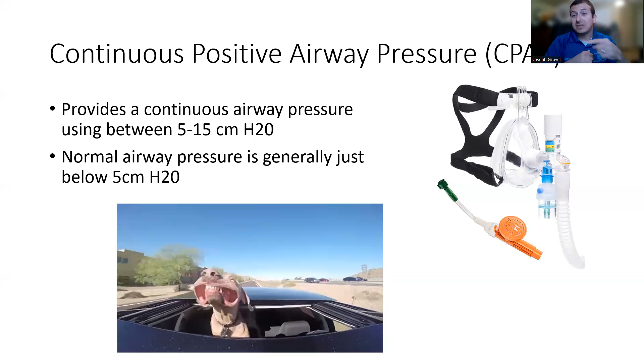So you create a minimum baseline as opposed to, right, where your normal airway pressure goes up and then down to 0. Here you're creating a force that's above that and continuing the pressure. And the hope is that continuous pressure will allow those alveoli to still stay open. So you don't have to keep addressing the fact that they've collapsed. If you keep the alveoli fully expanded, then the hope is that gas exchange is easier to occur. So once again, how does this help in some circumstances?